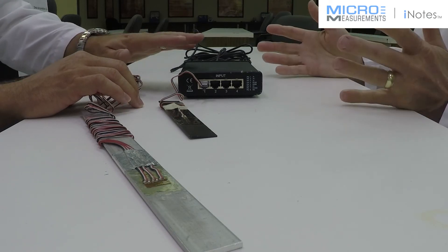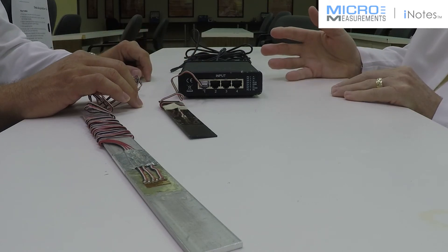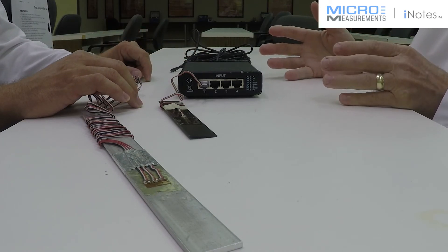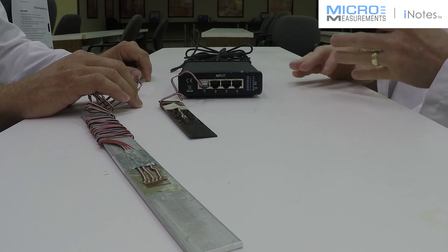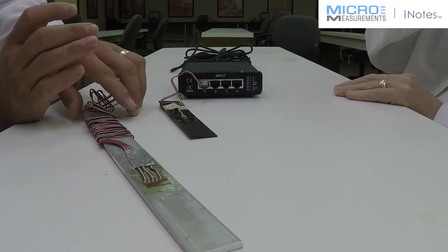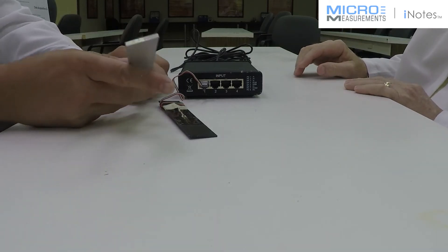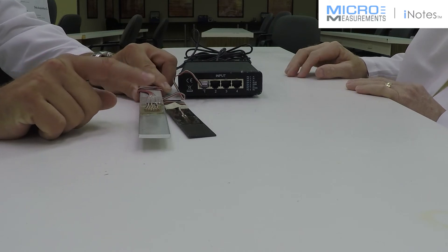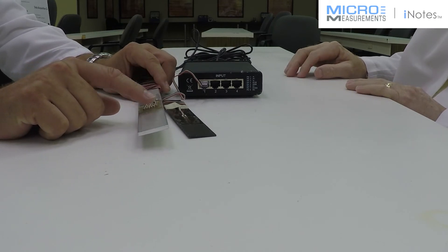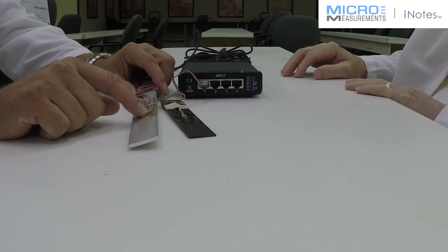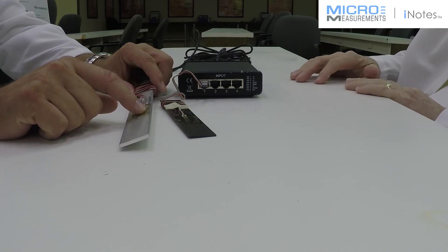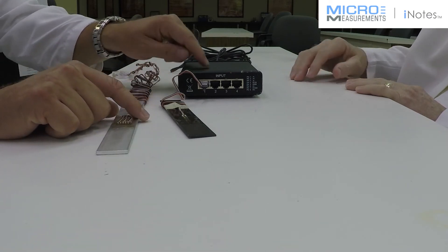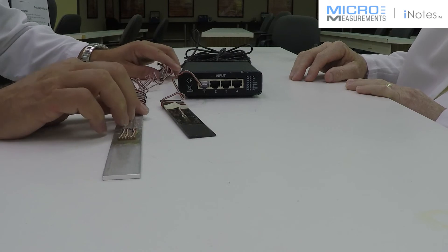It provides shunt calibration, bridge completion, all of the standard data acquisition instruments. So if I were using a rosette, what you're saying is I could use a 120 or 350-ohm, or even a 1,000-ohm rosette and connect it into that box. That's fantastic.